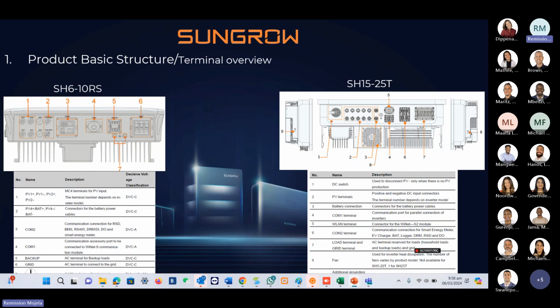And then we have the connector block, the basic structure of connection of the inverter. It's pretty much simple, to be honest. We have what you call AC in, which will be the grid part, and then we have the backup port, which is a plug-in on the 6RS. But on the 10, you actually terminate it because the current there is much higher, while on the 6RS it's just plug and play. You only terminate the grid side. And on the 15T and 25T, it's just plug and play as well. It's just plug-in for both grid and the backup port.